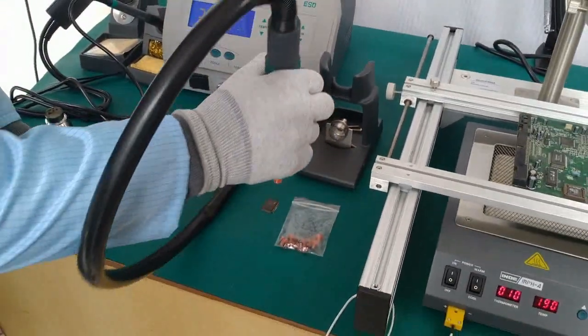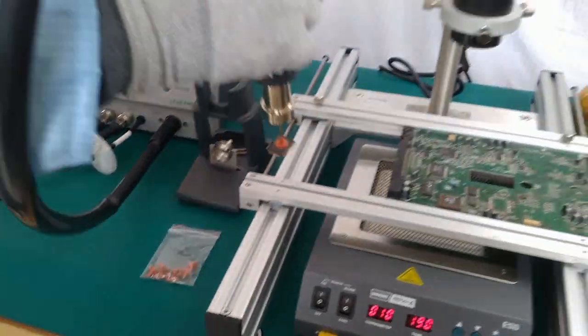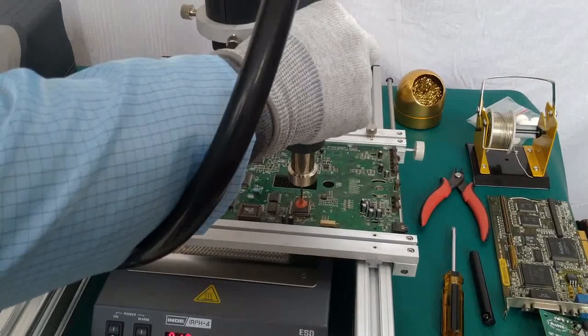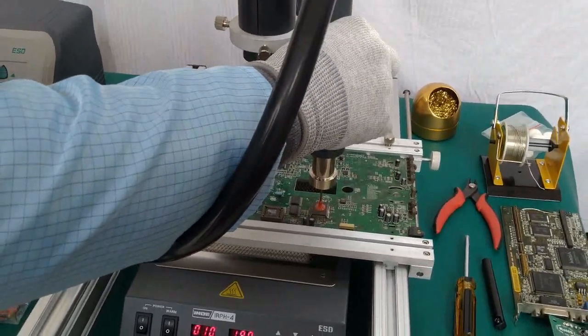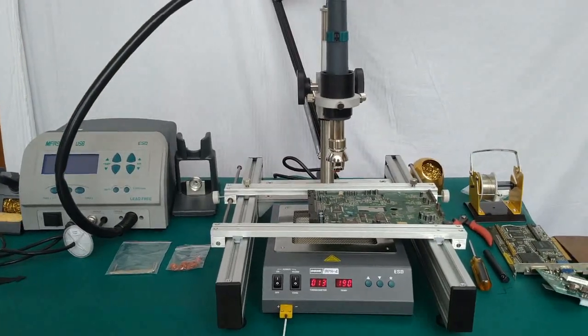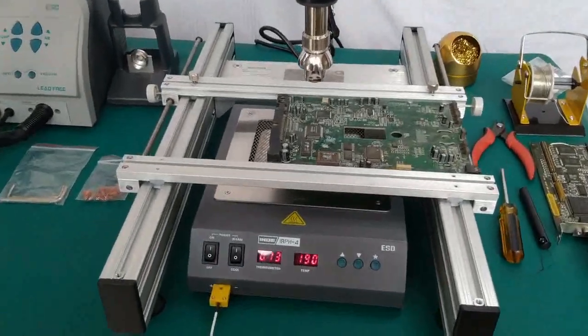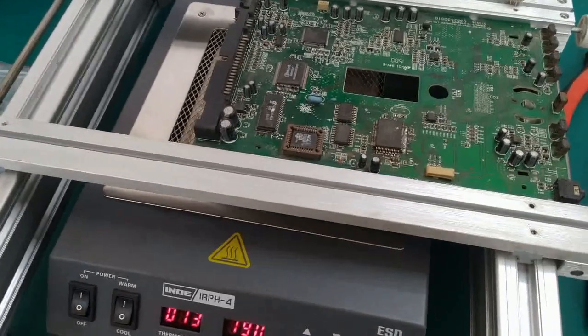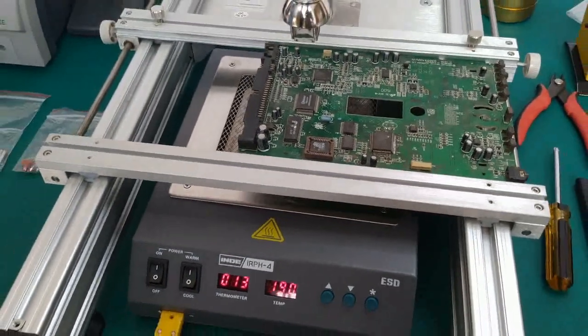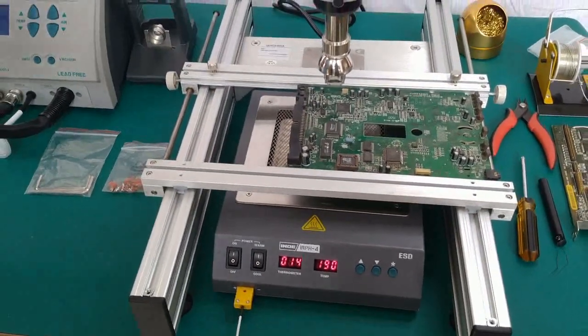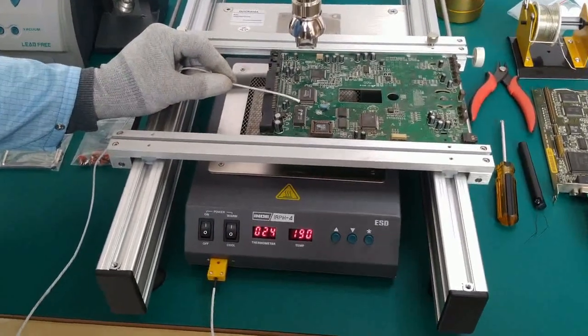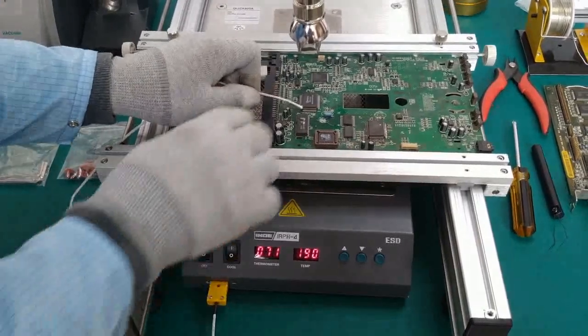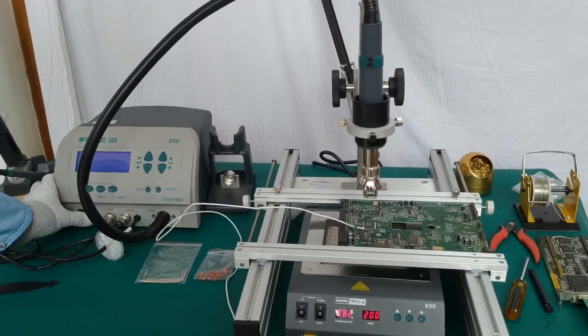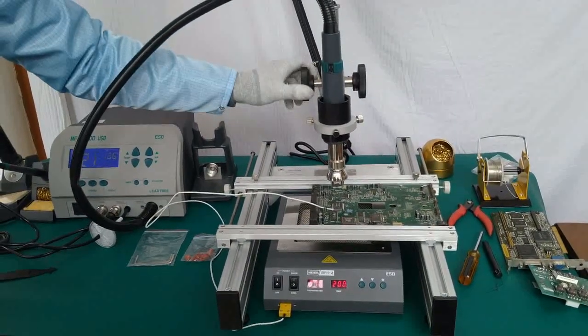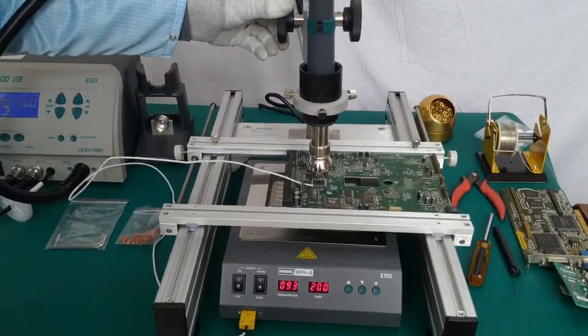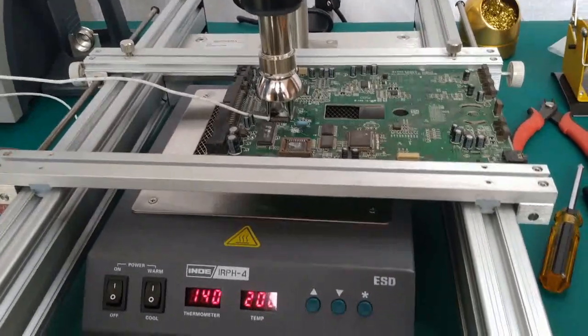Now the set temperature is 350 degrees, but the value observed on the thermometer is 367. We will input the value observed on the thermometer into this unit. We will first press tool 1, then we simultaneously press and hold the temperature up and down buttons. The unit will enter into calibration mode. We will input the value we have observed on the thermometer, that is 367, and then press the vacuum button. Now the offset value given to the unit is accepted, and we will then verify the temperature once again. Set and actual temperature is almost the same, and the soldering iron has been calibrated.